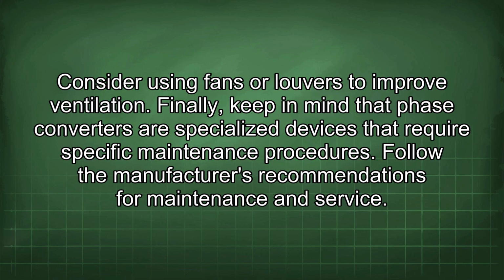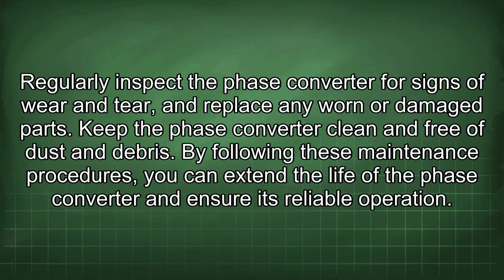Finally, keep in mind that phase converters are specialized devices that require specific maintenance procedures. Follow the manufacturer's recommendations for maintenance and service. Regularly inspect the phase converter for signs of wear and tear, and replace any worn or damaged parts. Keep the phase converter clean and free of dust and debris. By following these maintenance procedures, you can extend the life of the phase converter and ensure its reliable operation.